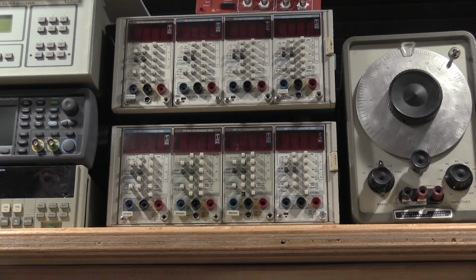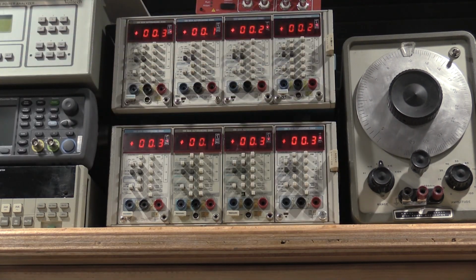So straight up from where we just were on the bench, we have the meter bank. These are two 4-bay frames, each with a DM502A, 3.5 digits. 3.5 digits is very capable for the bench and nothing to scoff at. I have found when I'm doing repairs that I need meters to do two things. I either need them to sanity check something, in which case I do not really care how many decimal places it can get out to, in which case these perform exceptionally well. They also have a very, very good stability over time.